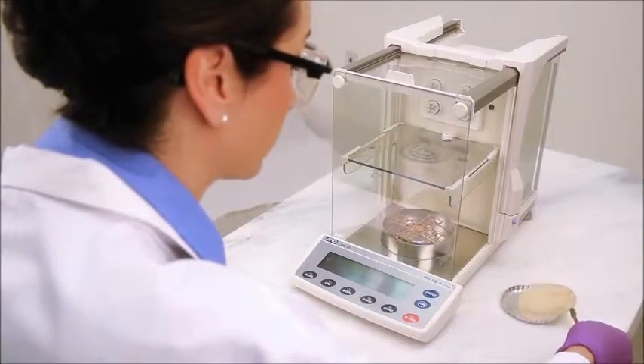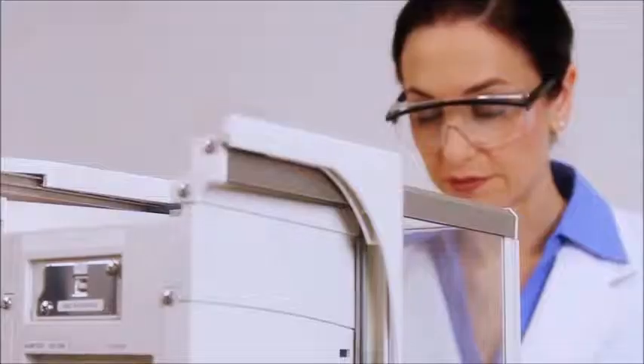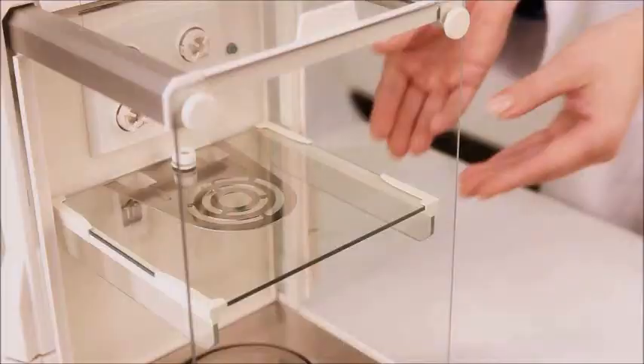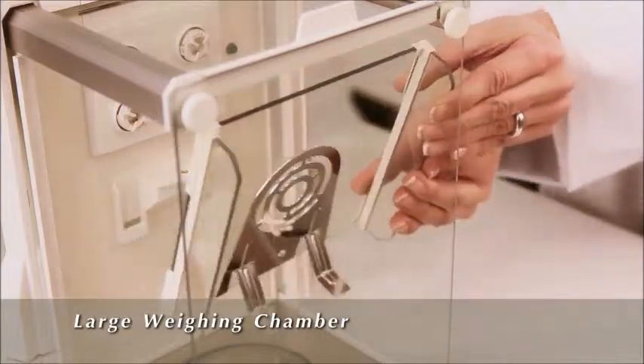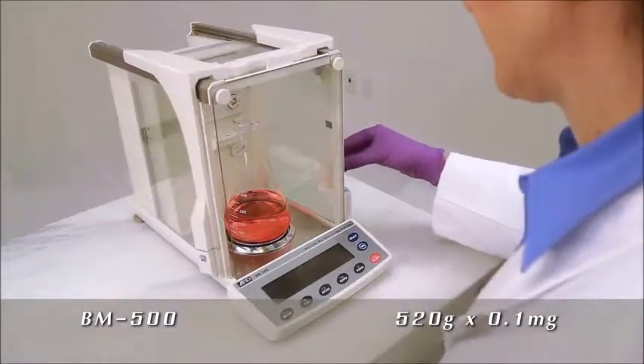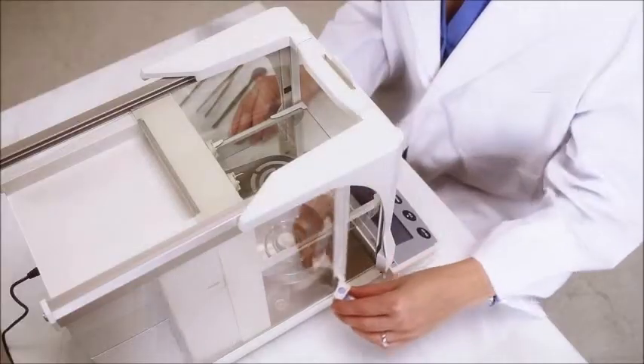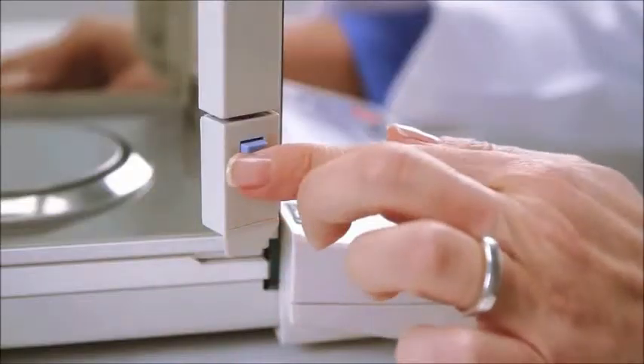Now there's a real choice when it comes to six-place balances. For five-place and four-place measurements, you can easily weigh taller objects in all six models simply by removing the shelf, including the BM500 with its 520-gram capacity. Interlocking doors make weighing more efficient because either door can be opened by the opposite hand, or both doors with one hand.